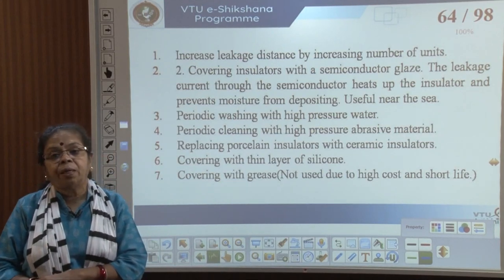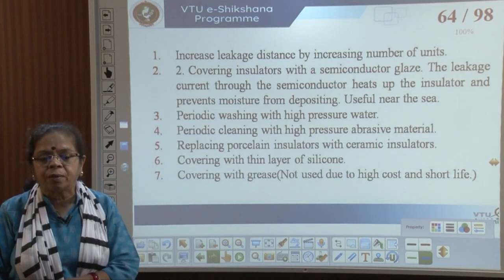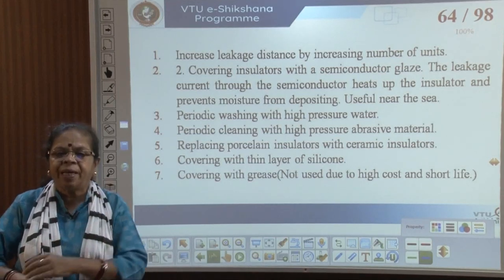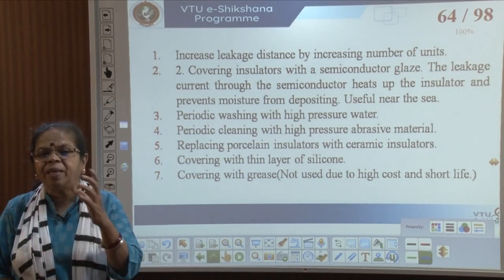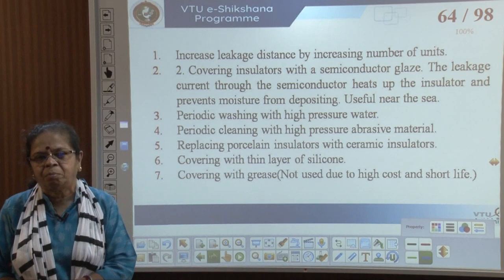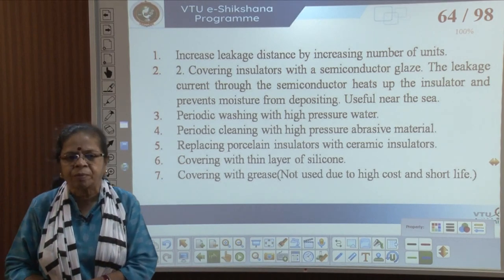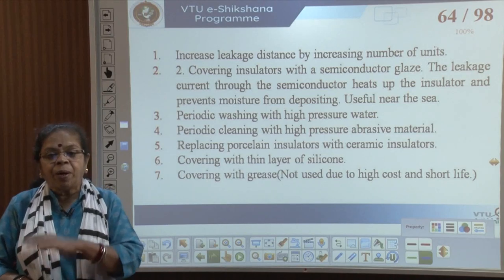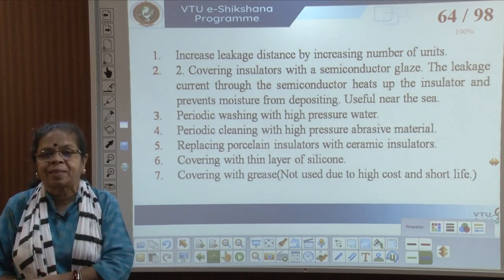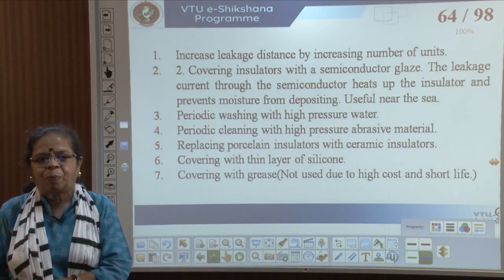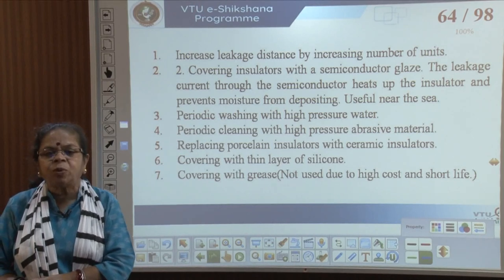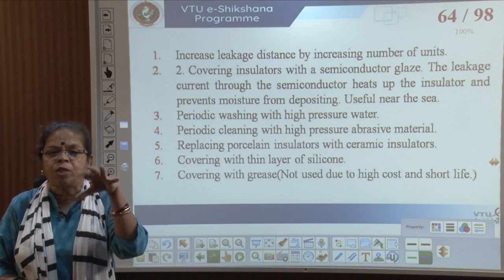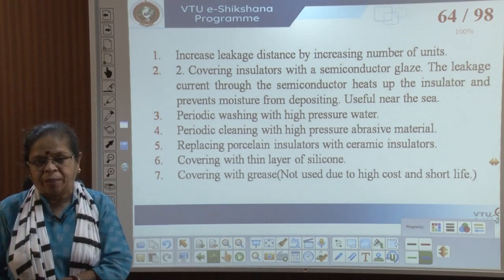To reduce chances of flashover, we can increase the leakage distance by increasing the number of units — but that increases cost. Insulators can also be covered with a semiconductor glaze; the leakage current through the semiconductor heats up the insulator and keeps it warm so moisture does not get deposited on it.